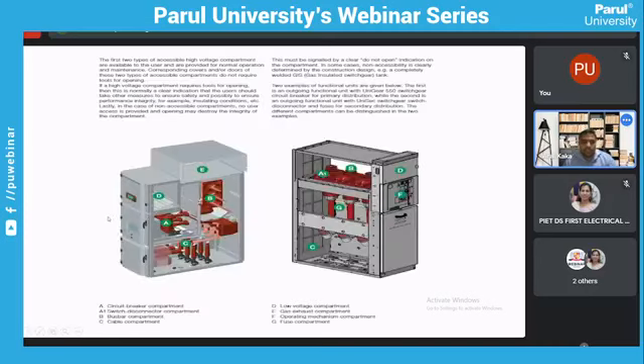These are the compartments. I have just shown a top line overview of what exactly the medium voltage circuit breaker is in terms of compartments. A comes with a circuit breaker compartment, B comes with the bus bar, low voltage compartment, gas duct compartment. Now the gas duct compartment also plays an important role whenever you are installing the switchgears in any substation or any e-houses or a complex substation. So you need to design an e-house or the substations where all these gas ducts are connected together across the switchboard and then it's been vented outside the substation or e-house.